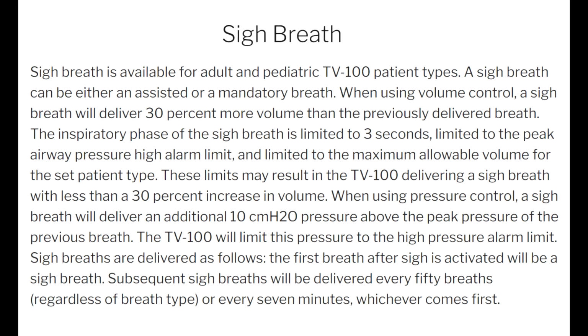Sigh breaths are delivered as follows. The first breath after sigh is activated will be a sigh breath. Subsequent sigh breaths will be delivered every 50 breaths, regardless of the breath type, or every 7 minutes, whichever comes first.